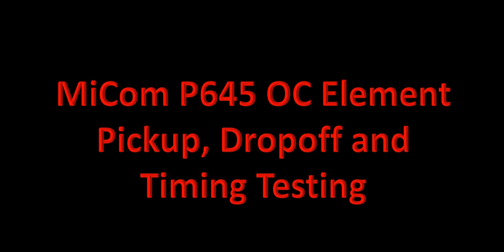In this video, we're going to use the knowledge we learned so far to do practical testing for the MiCOM P645 overcurrent element. We're going to test the pickup, drop-off, and timing using the CMC 356 test set. We have done some settings for the MiCOM to pick up at 1000 amps primary. Before we can proceed to that test, we need to configure the MiCOM P645 to publish GOOSE messages.